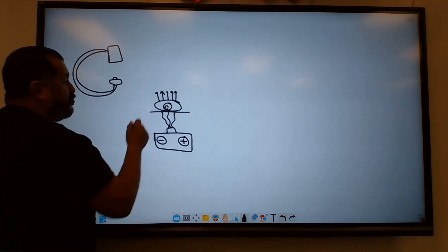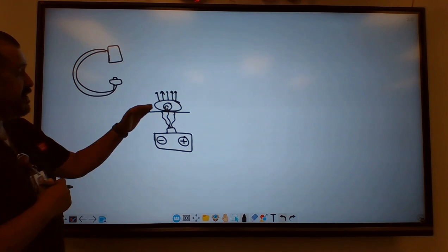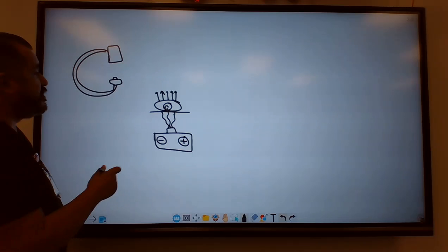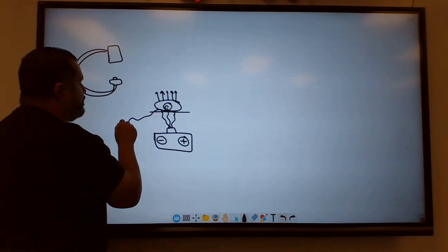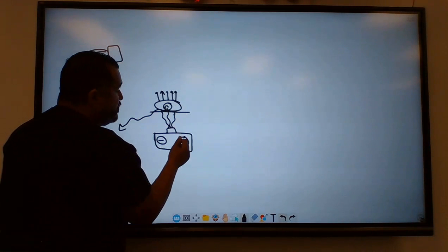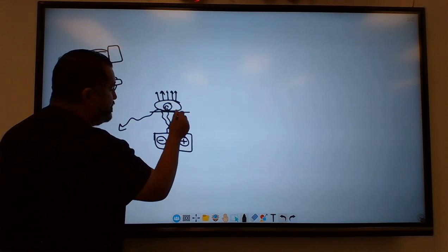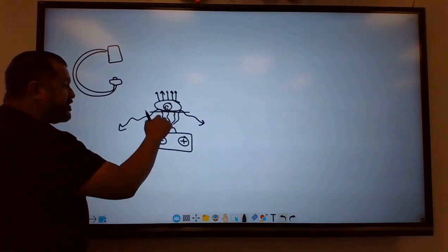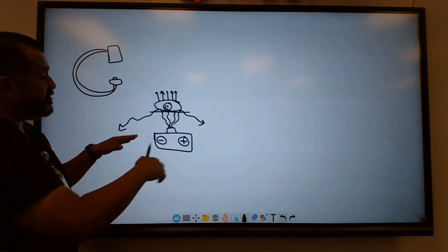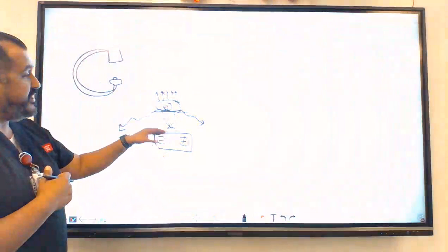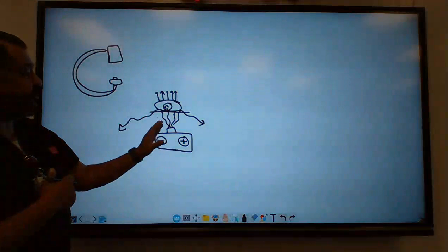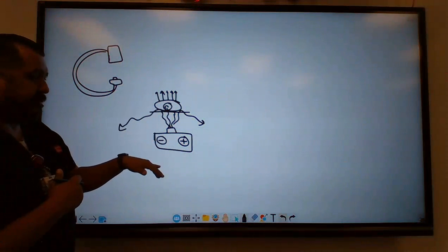We call this the exit or remnant radiation—it's the leftover primary beam. You're still going to have some scatter, and believe it or not, the reason the X-ray tube is on the bottom is because when scatter is produced, you want it going down towards the floor. That's why it's preferred to have the X-ray tube on the bottom rather than on top with the intensifier on the bottom. You want the scatter to go downward.